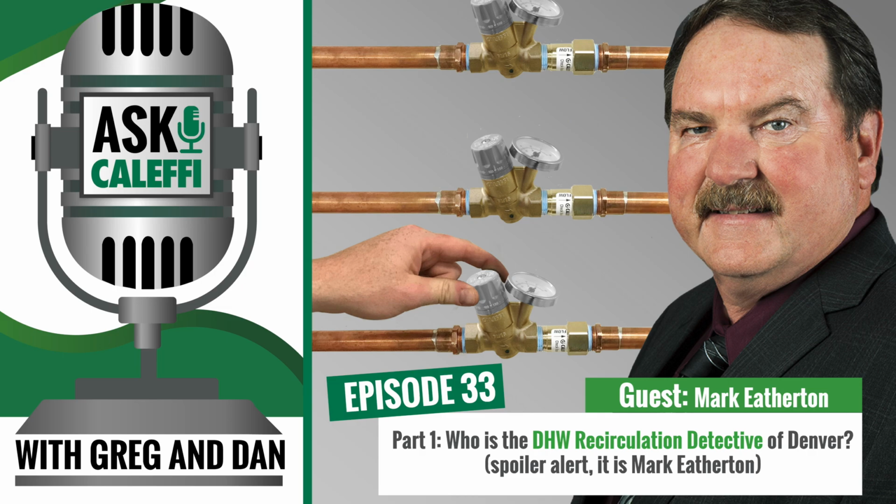And at the top floor, they're mixing hot and cold water in an effort to try to give them a constant common temperature. Relating to the nature of the complaint and where the complaint's coming from is going to give you some guidance on where you need to look. And that's one of the very first things that I check. When I go into a mechanic room, I like to be there during design conditions so that I can use my hands and my eyes and my ears to listen to the system and feel and see what's going on.